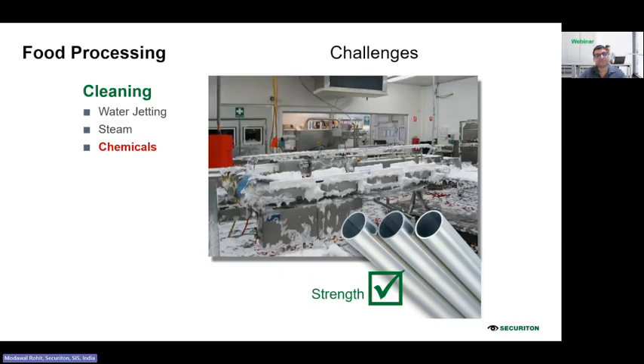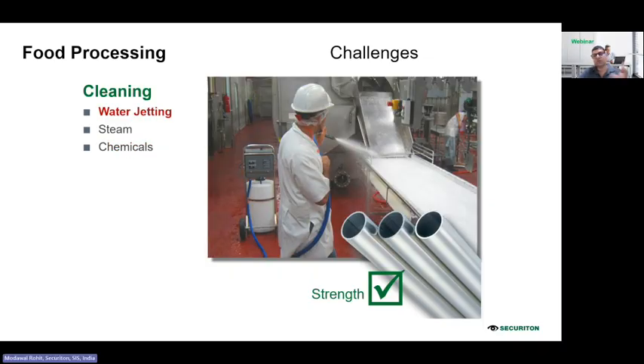Water jetting: you always use high pressure water jets because of the high hygiene requirements. So the detector must withstand IP65 or IP66 rated protection because of the splash of water. Otherwise, it will destroy the optics or the chamber of the detector. Sensitive components are always at risk of damage in this kind of environment.